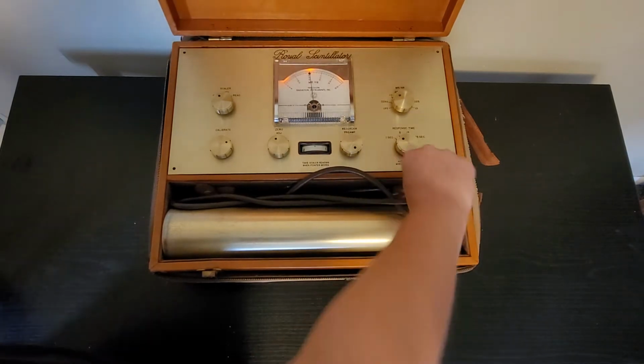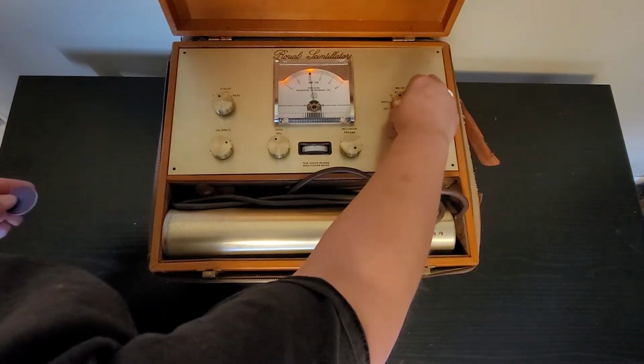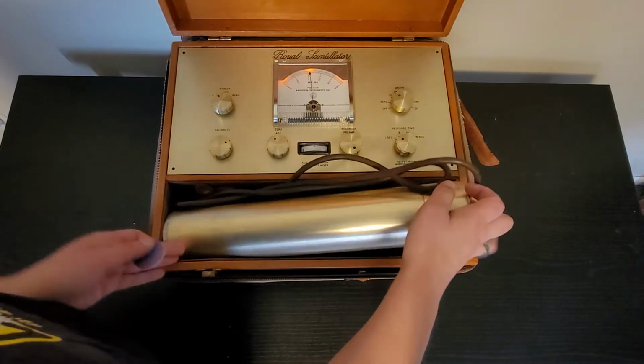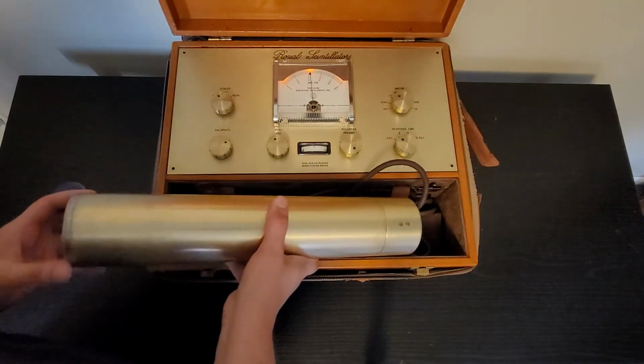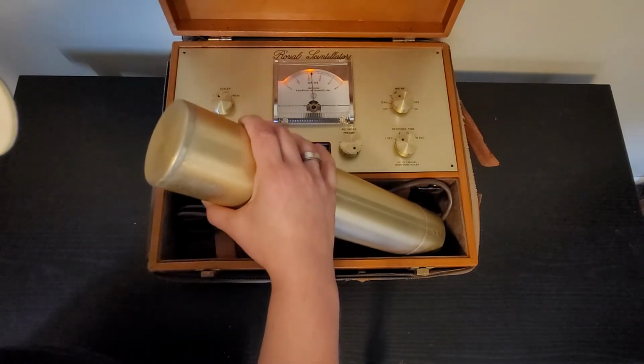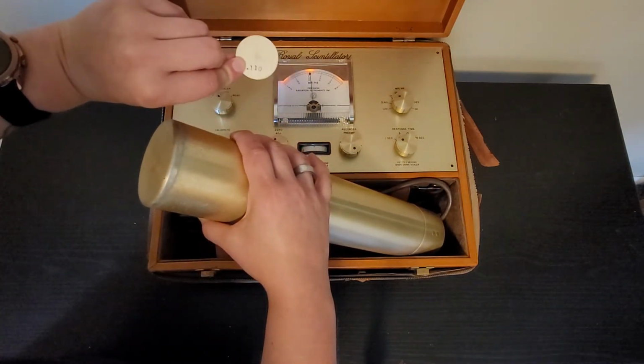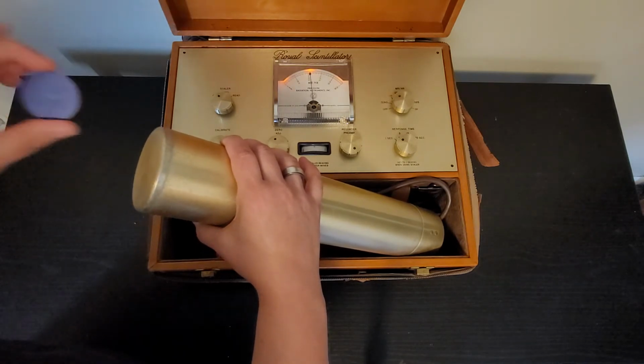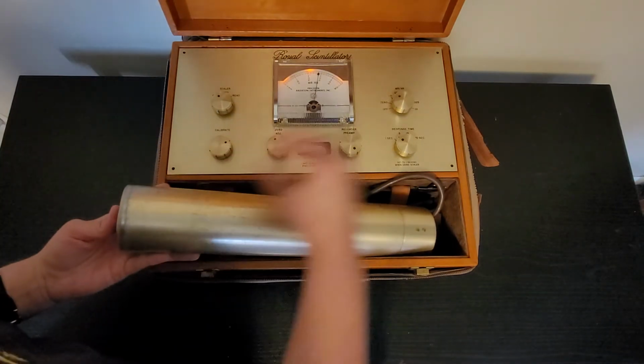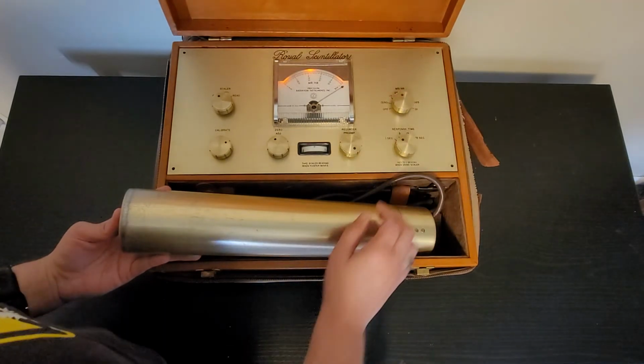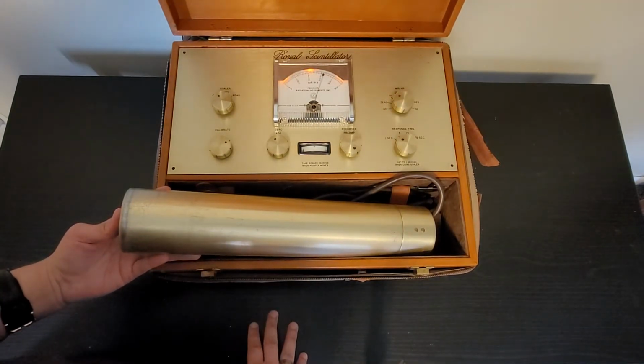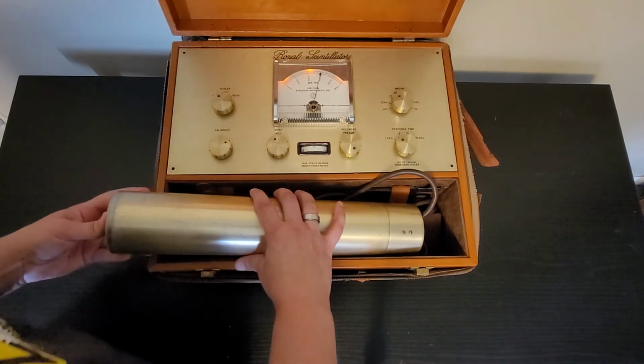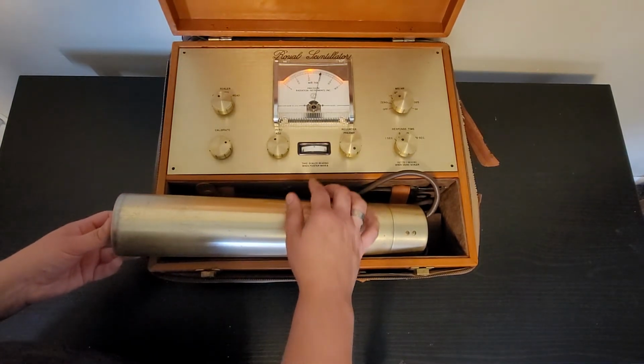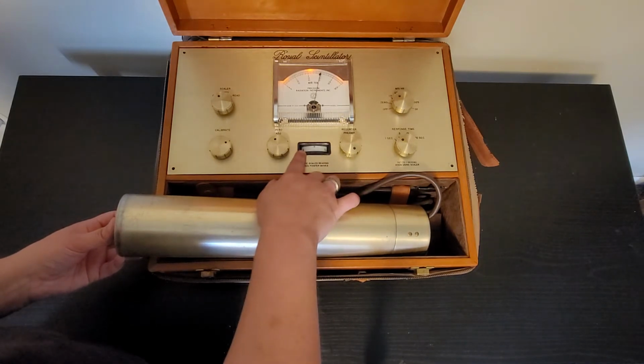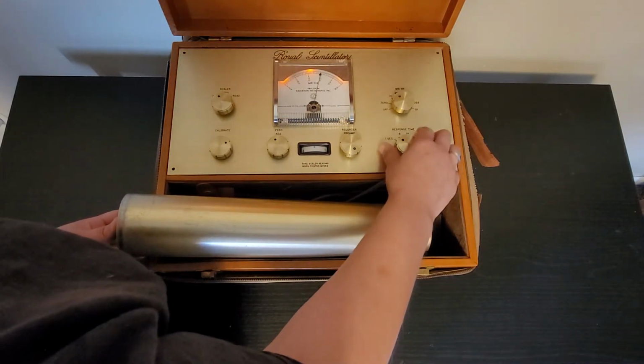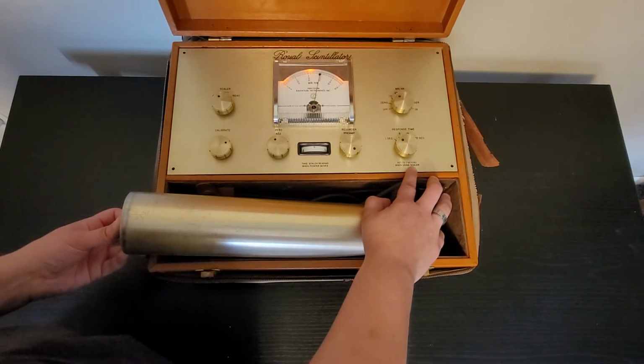So it has its own little check source in here. I'm not sure, this 0.110 it's marked. I'm not sure what actually is in here. But there it is on the 0.1 setting. Now, the scaler has a little needle. It counts for a minute and it moves the needle. So here it says set to 1 second when you're using the scaler.